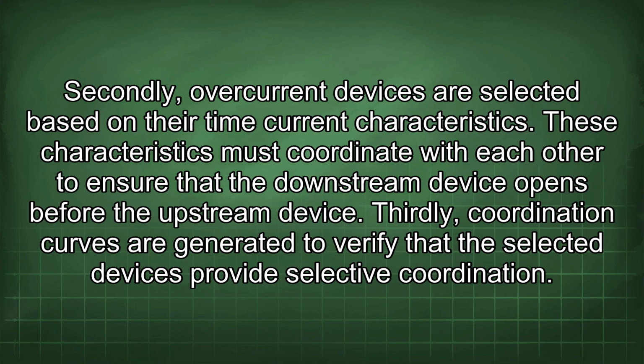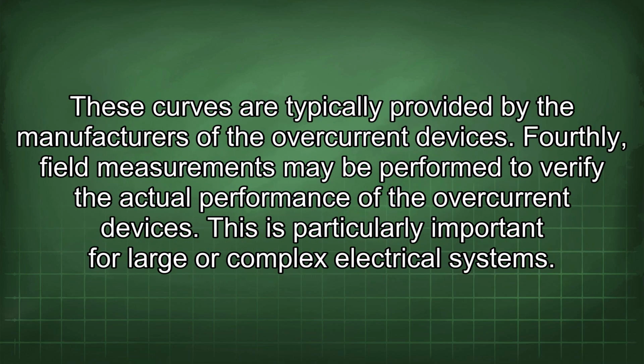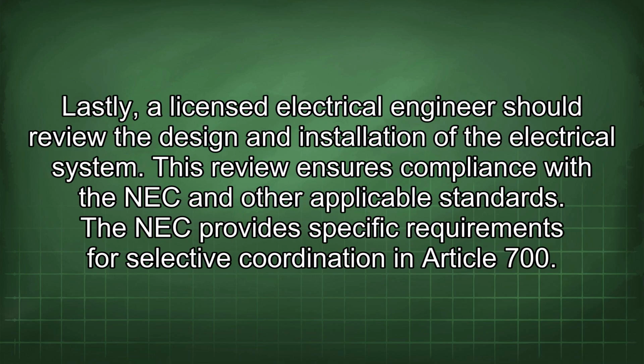Thirdly, coordination curves are generated to verify that the selected devices provide selective coordination. These curves are typically provided by the manufacturers of the overcurrent devices. Fourthly, field measurements may be performed to verify the actual performance of the overcurrent devices. This is particularly important for large or complex electrical systems. Lastly, a licensed electrical engineer should review the design and installation of the electrical system. This review ensures compliance with the NEC and other applicable standards.